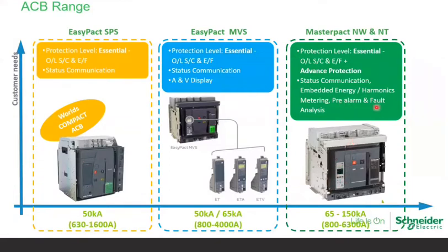By using that, if we connect this breaker to further devices like IFE and IFMs, we can get the pre-alarm. So what is an example of a pre-alarm? If your breaker is under overload, before your breaker is going to trip, you will get an alarm notification: your ABCD breaker is under overload, and after this much time, it is going to trip.